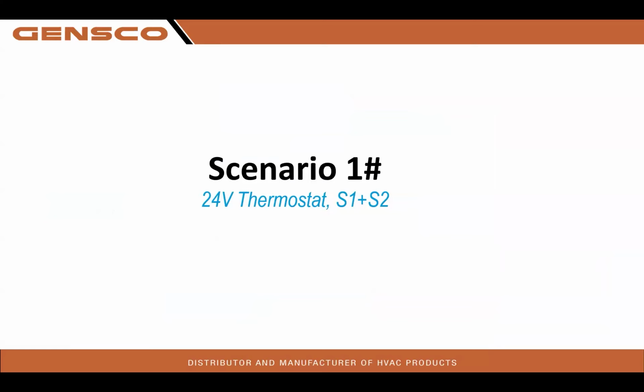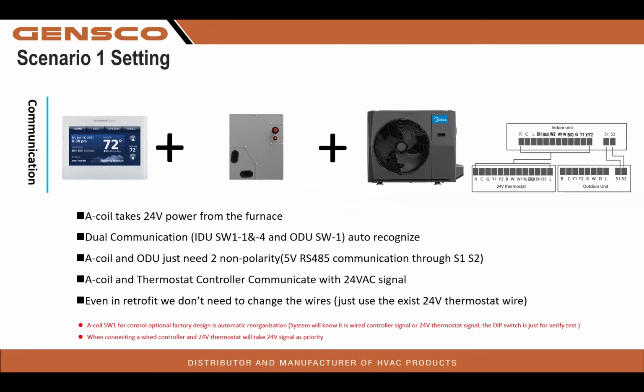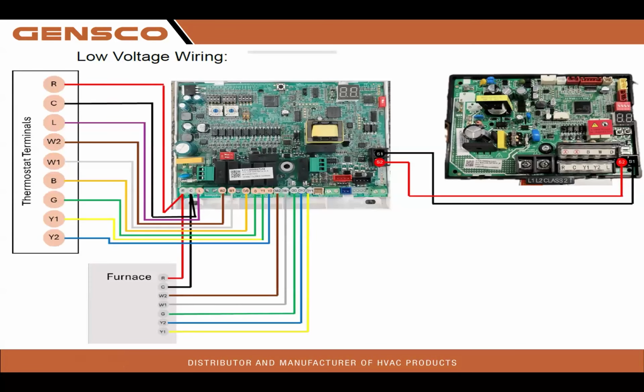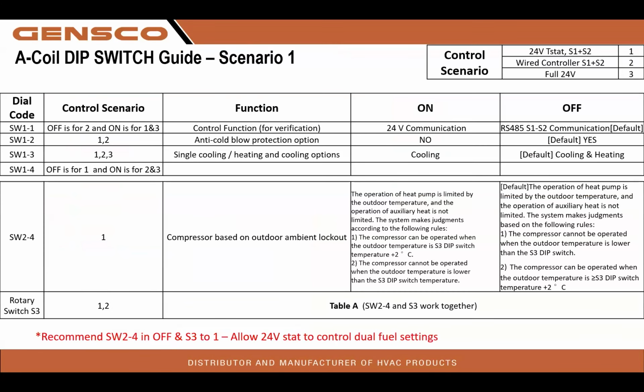Scenario number 1: 24-volt thermostat, S1, S2. So basically, we're going to be running a 24-volt conventional thermostat and S1, S2 to the outdoor unit. Here we have a Prestige 8000 coil outdoor unit. We are merely going to use our 24-volt controls from the thermostat to the indoor board and S1, S2 to the outdoor unit. There is a look at our low voltage wiring and the standard dip switch settings that we have already discussed.